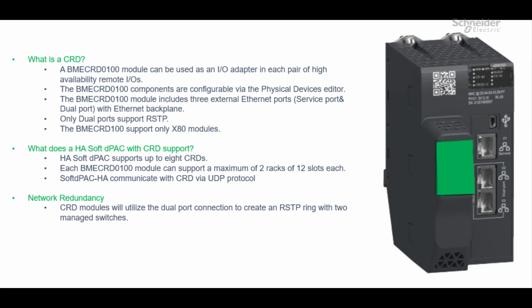Note that only dual ports support RSTP, Rapid Spanning Tree Protocol. The CRD module is configurable from Physical Devices Editor for the topology part, and HW configuration section for the I/O configuration. A high-availability soft DPAC supports up to 8 CRDs.